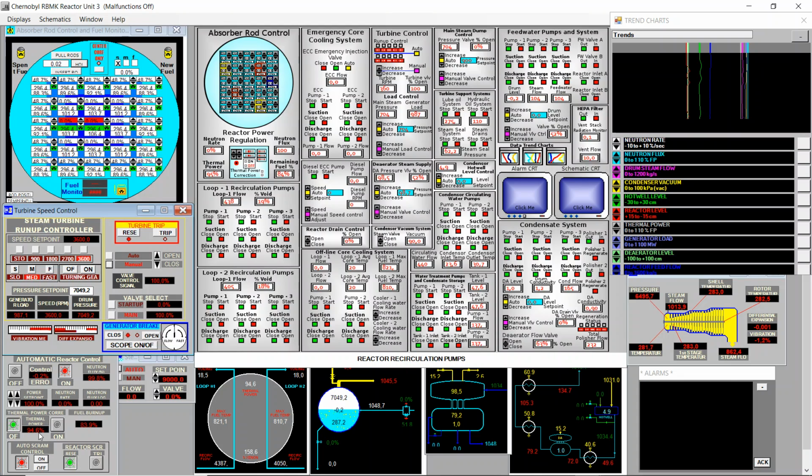Thermal power 94.6%, neutron flux 99.8, and in the inner core the control rods are withdrawn at 100%, or inserted at 0%, and in the rest of the core they are inserted at 48%. So we have very little available reactivity left. We have the Xenon decreasing, so hopefully we don't need to withdraw too many rods during the next hours, because the Xenon decrease will compensate for this reactivity need.